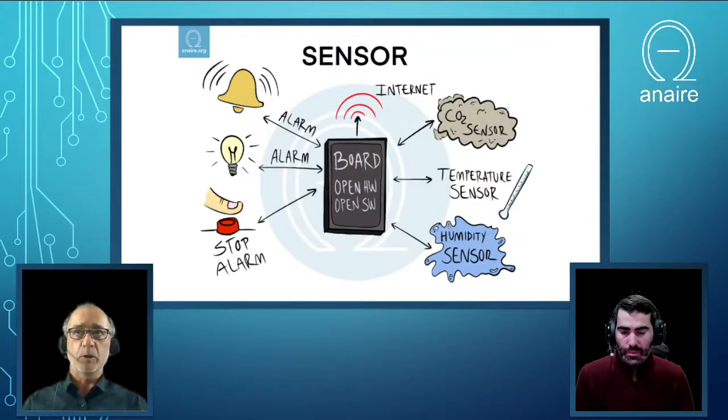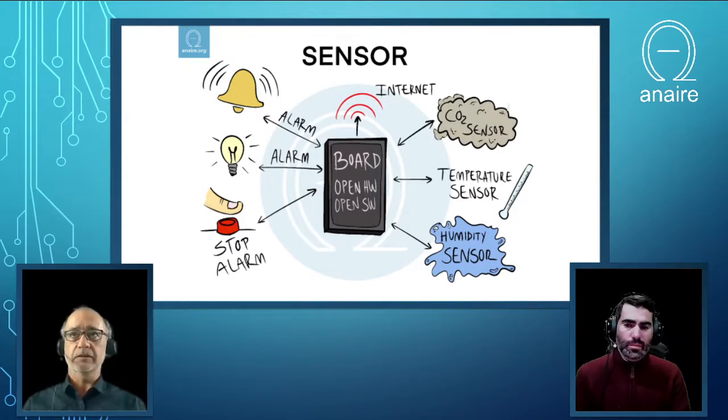The devices we are developing are also able to locally provide alarms and indications if there is a risk in the current situation. They will continuously monitor CO2, temperature, and humidity through different sensors, and will trigger an audible and also a visible alarm when the CO2 concentration surpasses predefined thresholds that can be configured to adapt to different situations. There is also one button to press to stop the sound if desired, so they can continue working or giving classes, but with the ventilation in place.